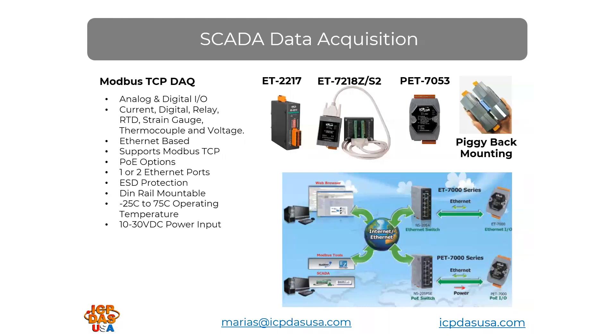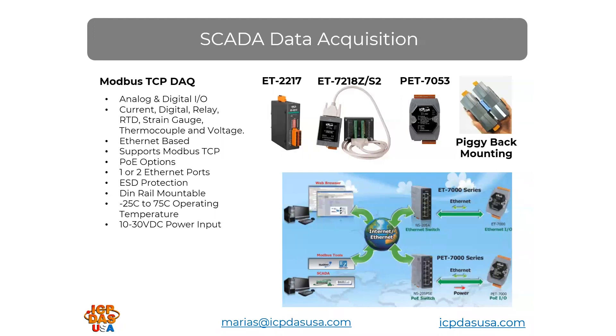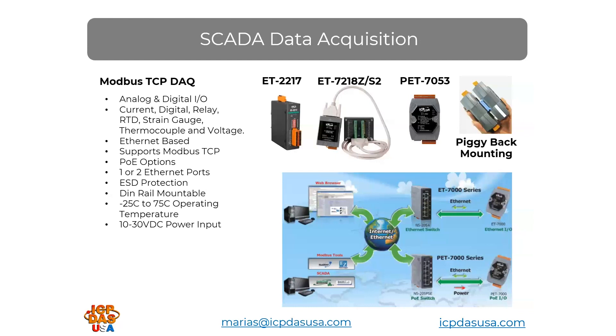SCADA software applications communicate with PLCs, controllers, and data acquisition equipment through software drivers. AVEVA Edge comes with over 250 native communication drivers for lots of different kinds of equipment, including Modbus TCP drivers that work with Modbus TCP data acquisition equipment like our Ethernet I/O modules. We have these Ethernet I/O modules. They can be DIN rail mounted and they can be stacked up to three high like piggyback mounting. They come in many different kinds of configurations, including analog, digital, current, relay, RTD, strain gauge, thermocouple, voltage, and more.